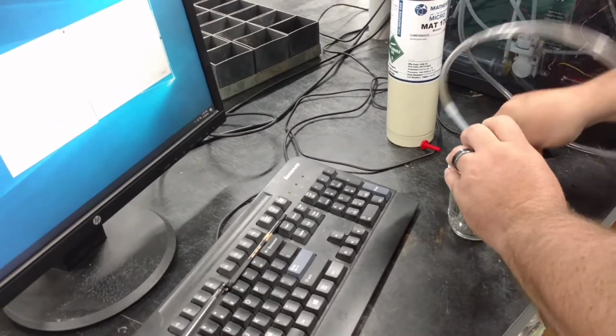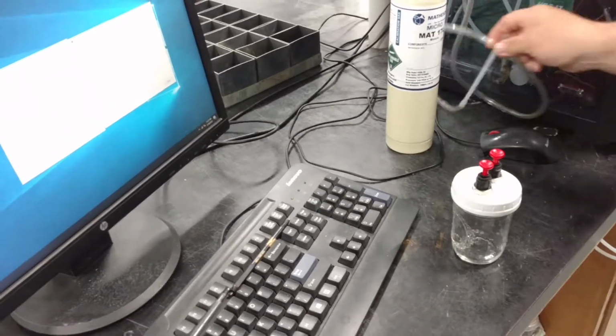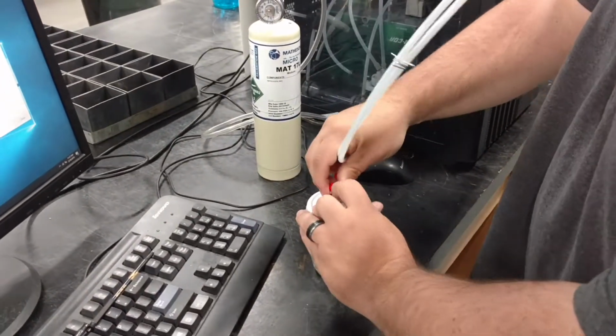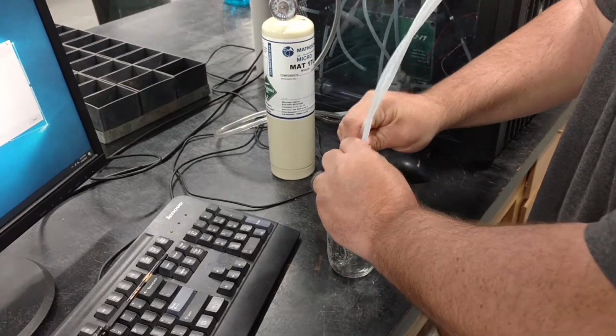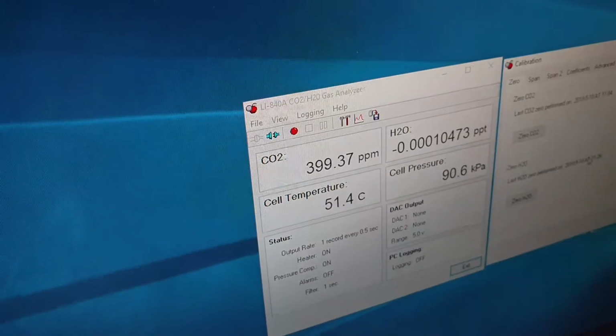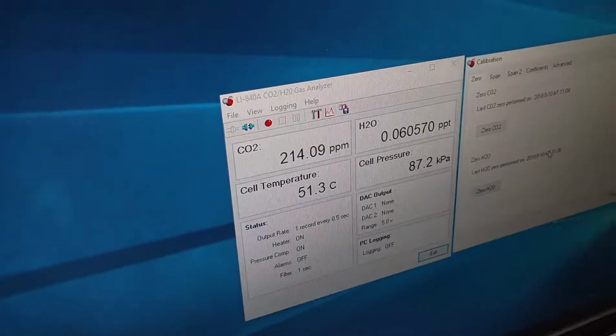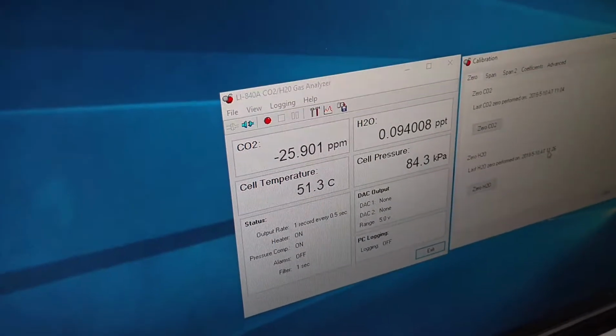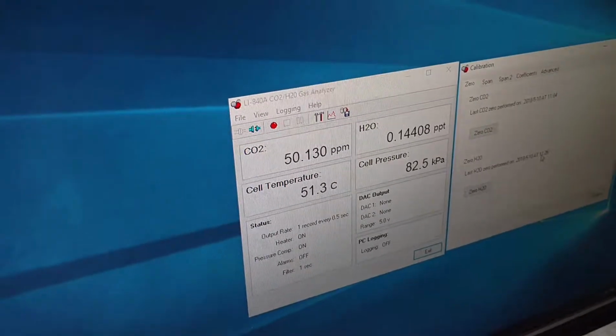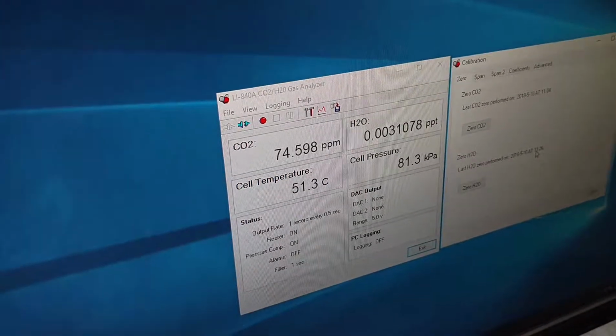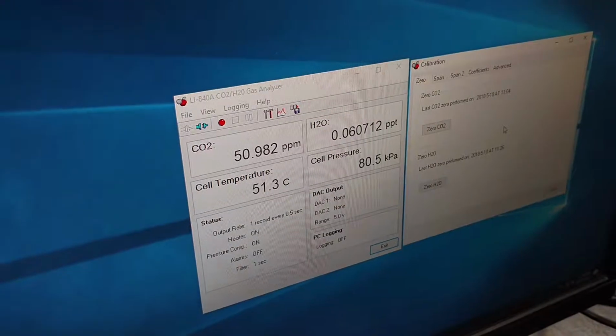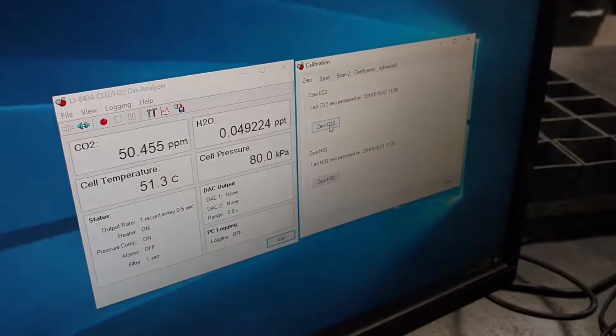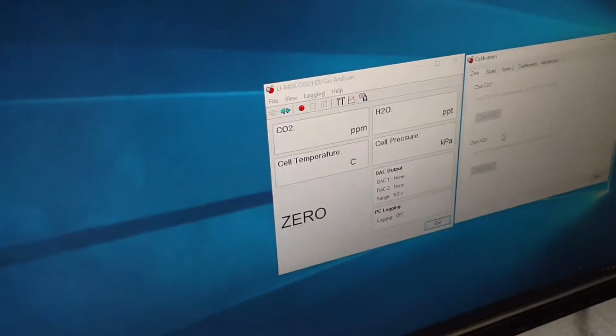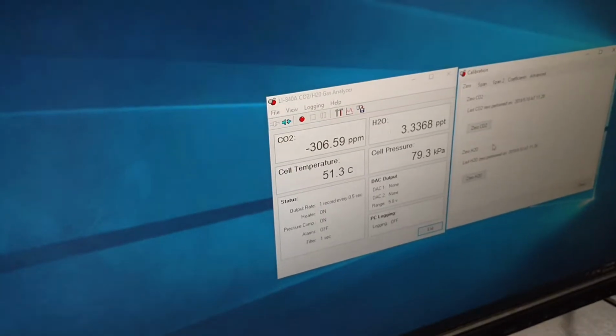Once your jar is filled with your calibration gas, you're going to shut off the regulator and quickly plug the jar using the 2 red plugs as part of your lid assembly. Now you're ready to connect the jar to your SR-1 instrument. As the calibration gas enters the SR-1 and flows over your detector, you should notice a change in readout in the Licor software. We want to allow 15 to 20 seconds for this readout to stabilize before capturing our 0 point calibration. Once the reading is stabilized, you're going to click 0 CO2 and Yes to allow the Licor software to capture this calibration point. Following capture, you should notice the CO2 reading somewhere near 0 on the Licor software.